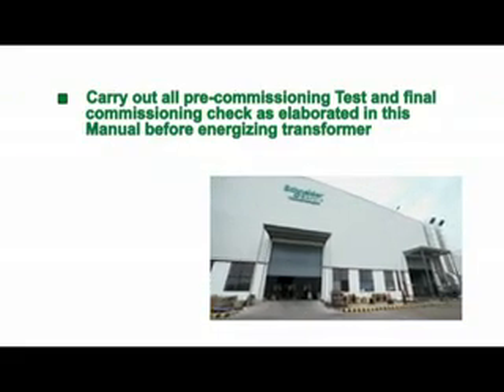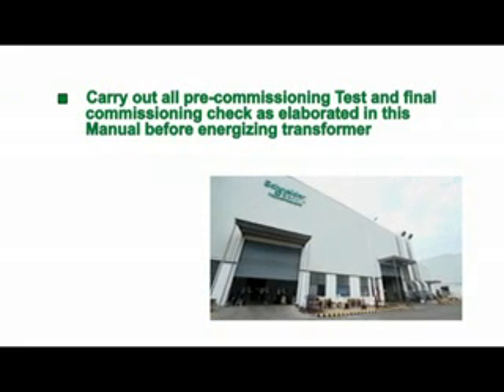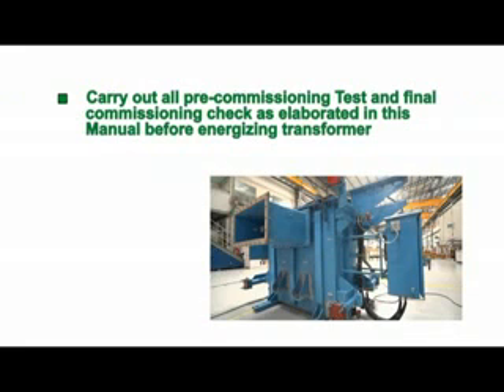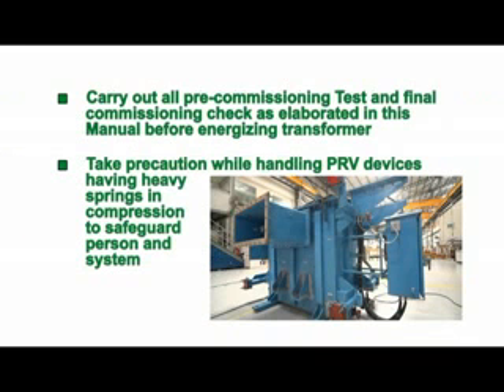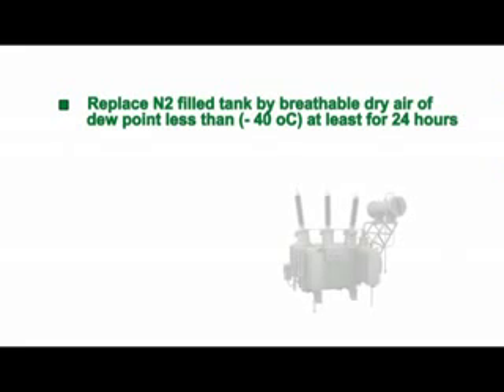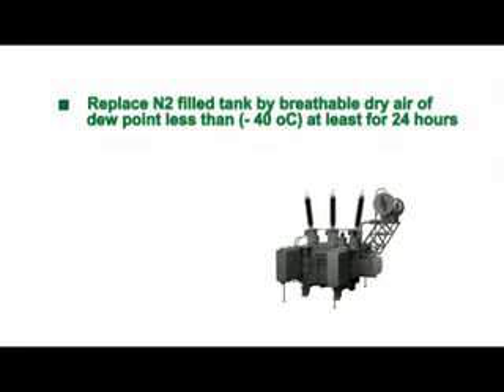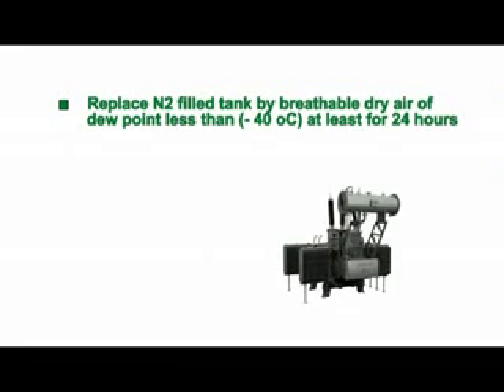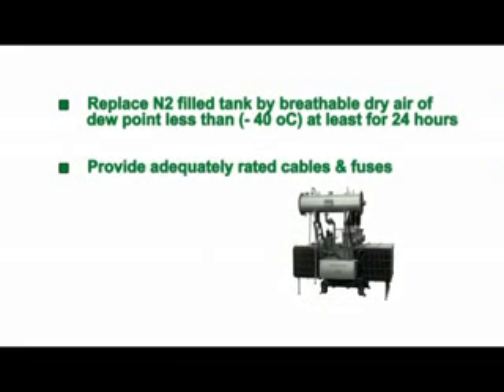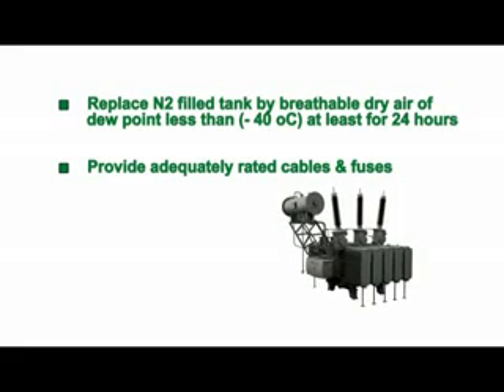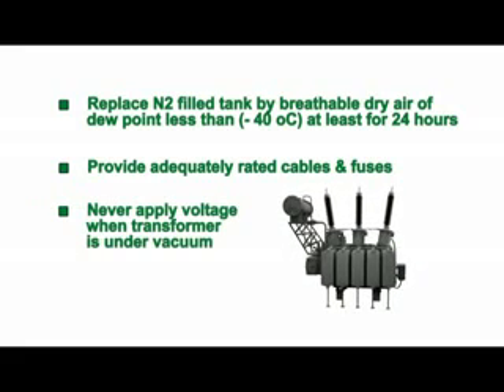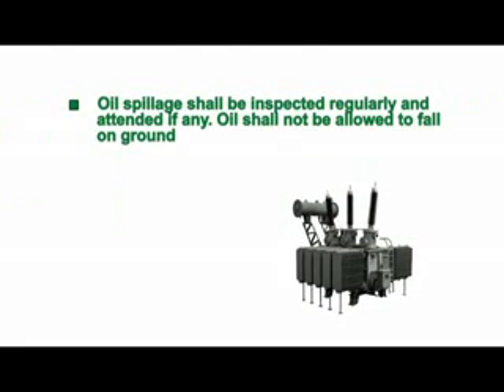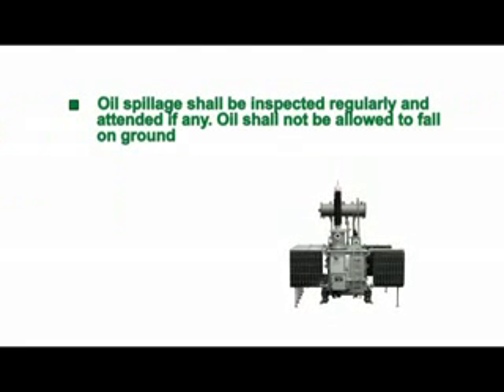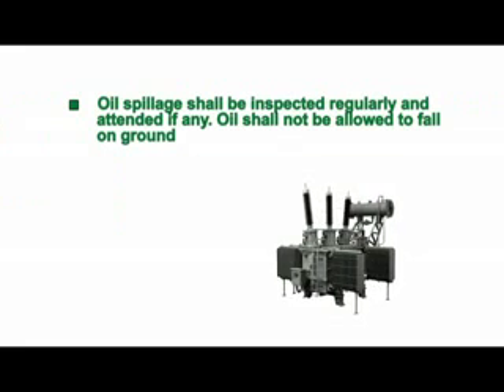Carry out all pre-commissioning testing and final commissioning checks as elaborated in this manual before energizing the transformer. Take precaution while handling PRD devices having heavy springs in compression to safeguard person and system. Replace N2 fill in the tank by breathable dry air of dew point less than -40°C, at least for 24 hours. Provide adequately rated cables and fuses. Never apply voltage when the transformer is under vacuum. Oil spillage shall be inspected regularly and attended to, if any. Oil shall not be allowed to fall on the ground.